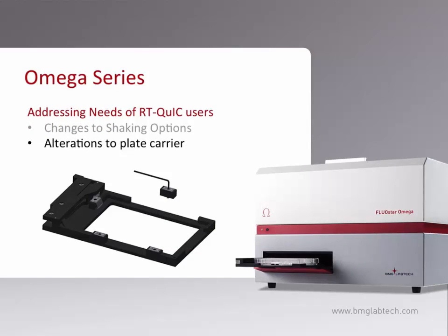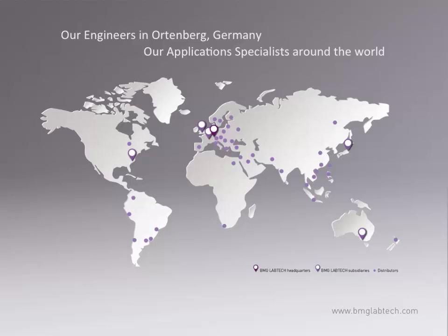During the robust shaking of the plate during the RT-QUIC assay, the possibility of a plate coming off the plate carrier was identified as a concern. To address this, BMG can now provide a plate carrier with clips designed to hold the plate more securely when the plate is pressed firmly into the carrier. These clips can easily be removed if you so choose. I would like to thank our engineers for designing the Omega as such a robust platform. Although it was not designed for RT-QUIC, it seems quite well suited to the task, and they have been instrumental in implementing changes helpful to RT-QUIC users.